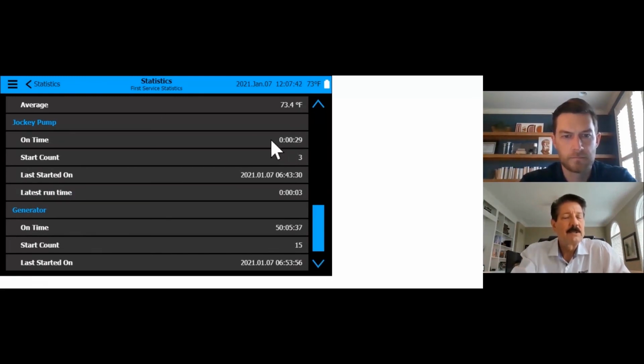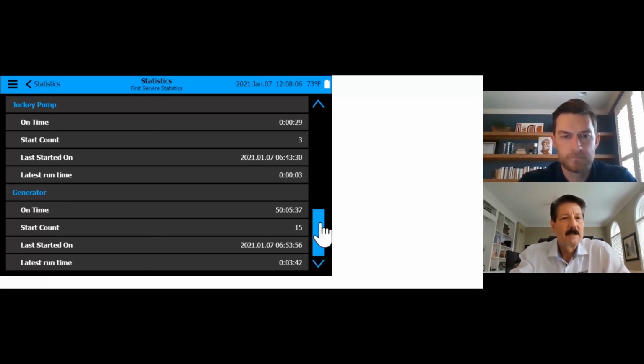Jockey pump, again, we do this by pressure. You have pressure starts dropping, and all of a sudden, as time goes through, the pressure comes back up above cutout. There's only one thing that's really going to cause that to happen: the jockey pump's going to operate, brings the system pressure back up rather than continue to drop and turn the main controller on. And we do that with algorithms in the software. And the same thing with the generator. We got the number of counts, the amount of time on a gen set. Last time it started, ran for 3 minutes and 42 seconds, which was today.